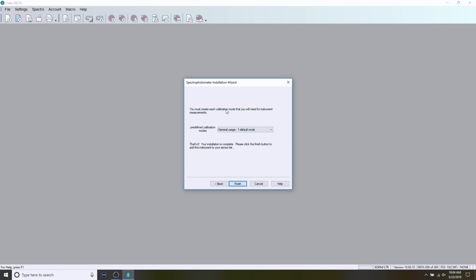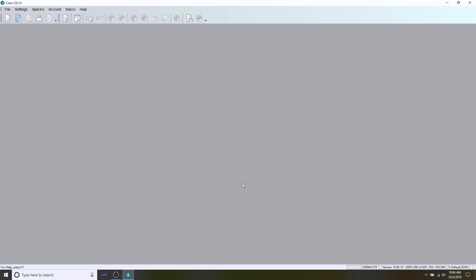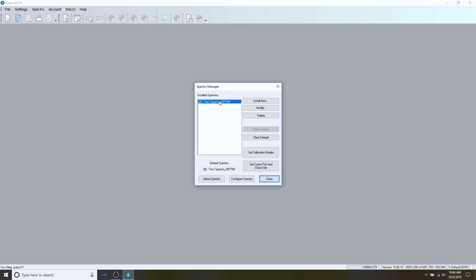And then finally I'm going to hit finish. It's going to always do a predefined calibration mode, and we'll look at those modes in just a moment. It's going to go out and try to talk to the instrument for a moment, and it appears that it worked because we got no error messages in response. Now, if I go back to this installer configure, you can see my Spectro. It's pulled the serial number of the instrument there.